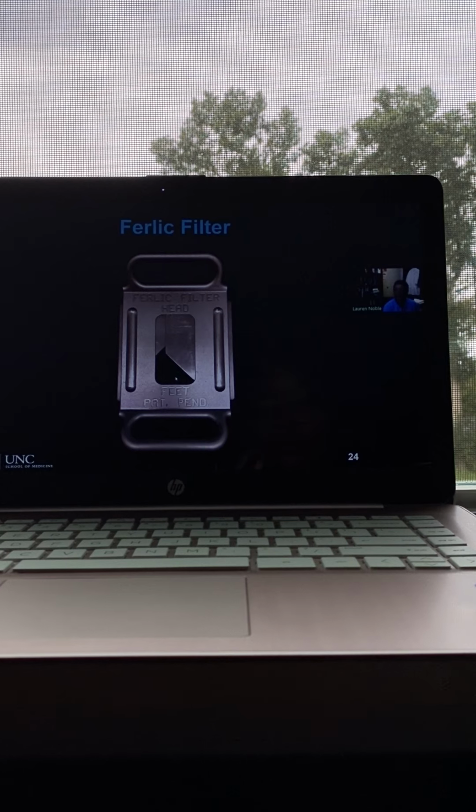If you're doing a C-spine, this part of the filter will absorb a fair number of x-rays for the upper C-spine. Whereas the bottom part of the filter, you notice there's a hole, that will allow more x-rays through so that we can get that lower part of the C-spine by the shoulder area. This way it prevents the upper C-spine from coming out too dark.